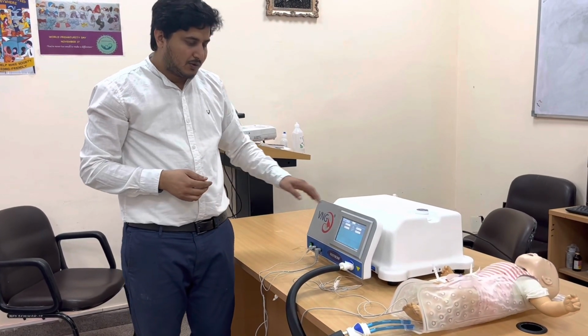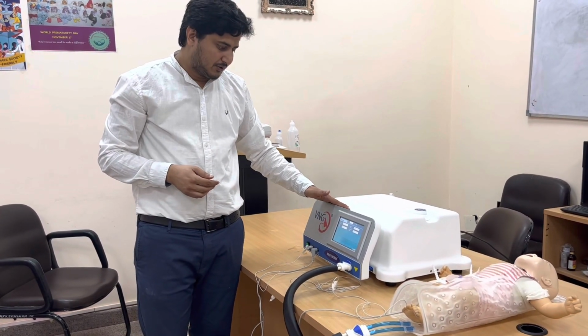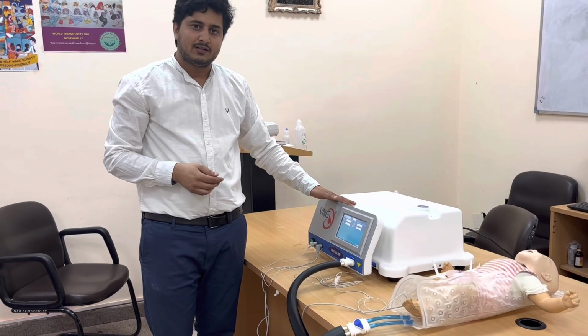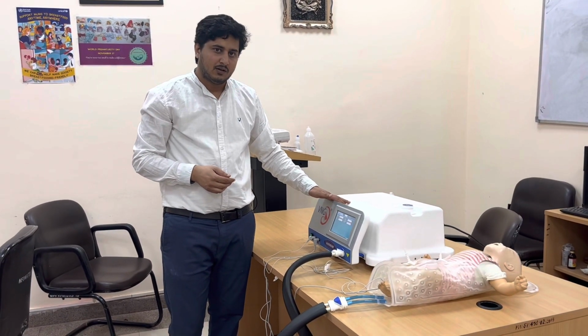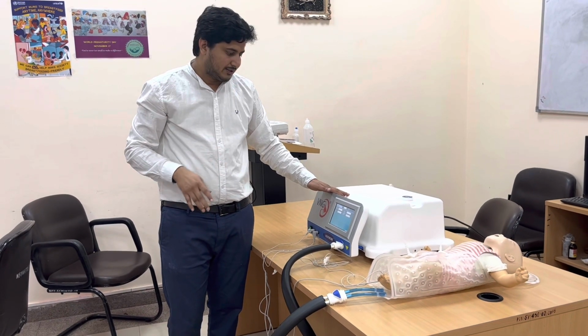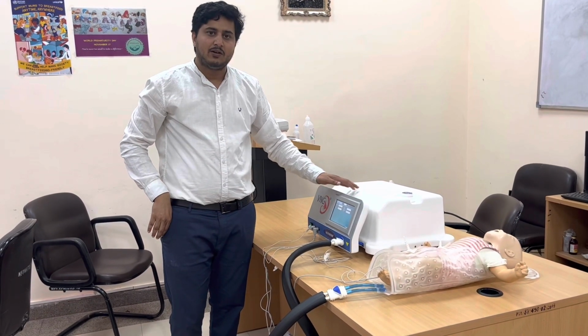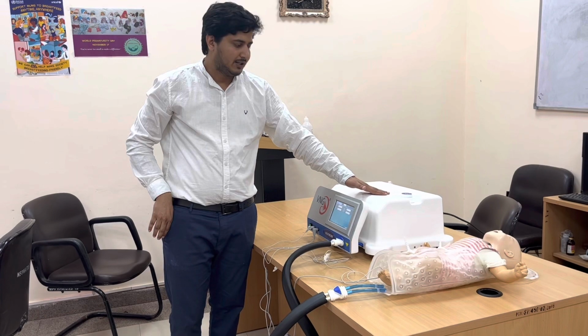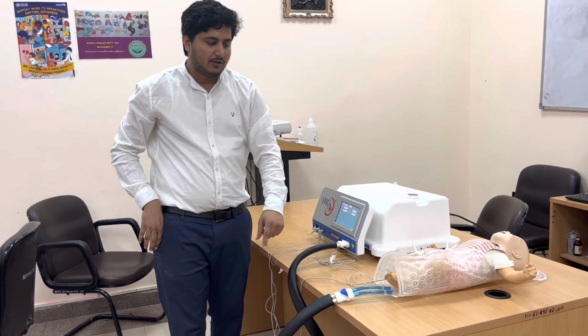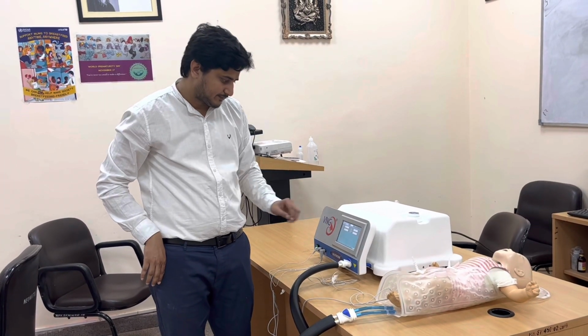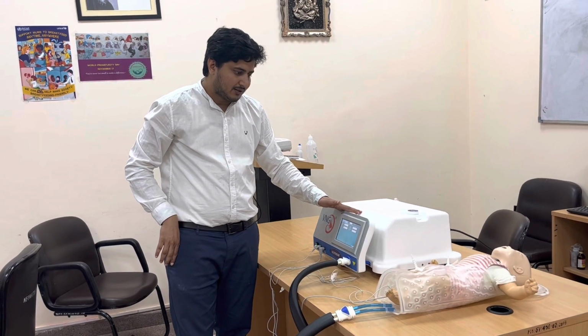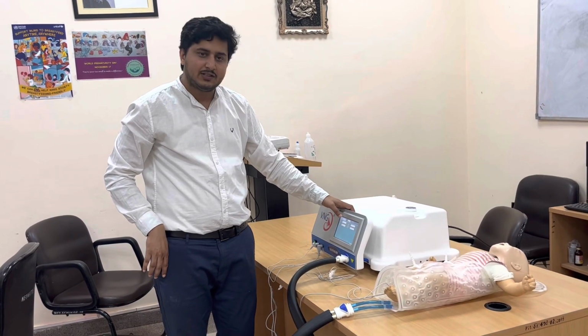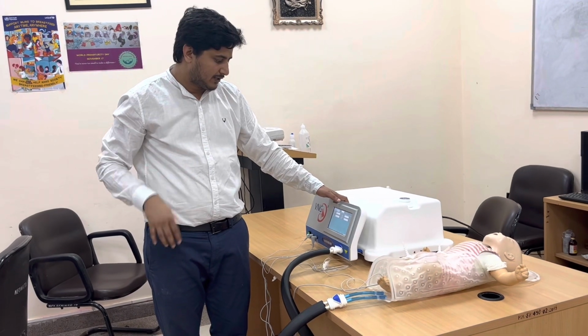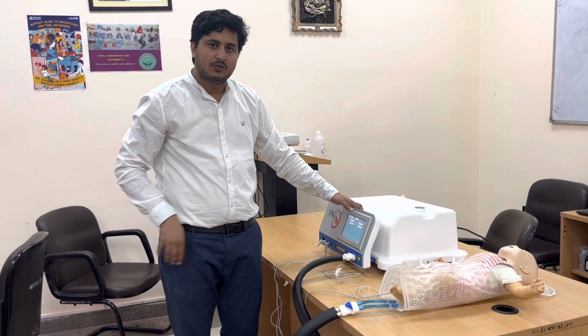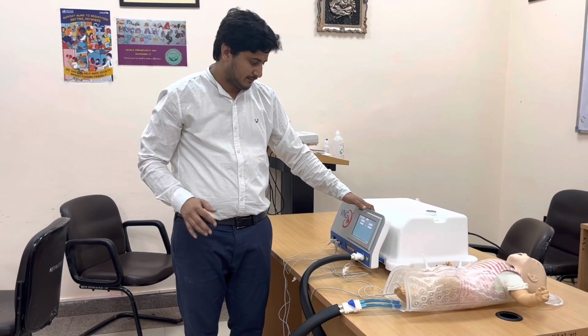Now let's move on to understanding the alarm systems and troubleshooting. This device gives alarm principally for 4 reasons. One is when the level of water is inadequate in the reservoir. Second, the flow rate in the cooling mattress is less. And the third is when the temperature deviation is +1 or -1 degree Celsius from your target core temperature. And the last one is at the point of device failure.